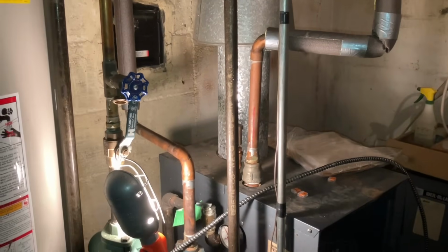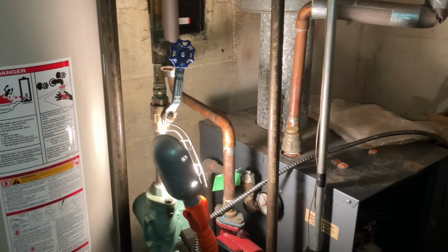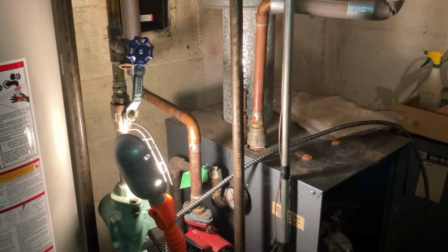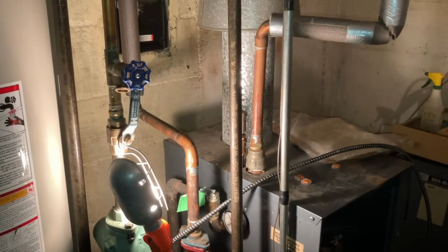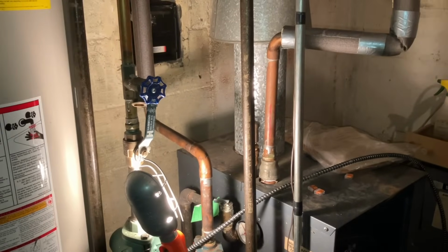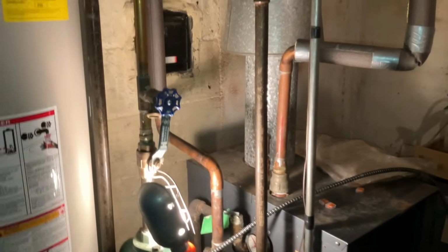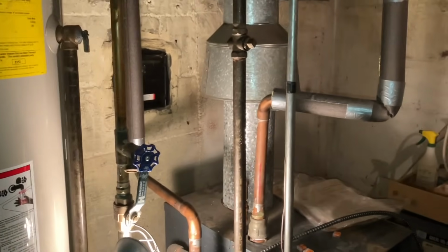When it's been holding back 40, 50, 60 pounds of pressure and giving only 12 on the outlet side for 20 years, 40 years undisturbed, you would touch that, it may not want to turn off. It may want to leak. It may not do anything. It may say, hey, listen, I'm comfortable here. I'm only giving 12 pounds.